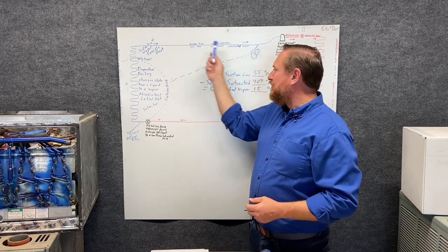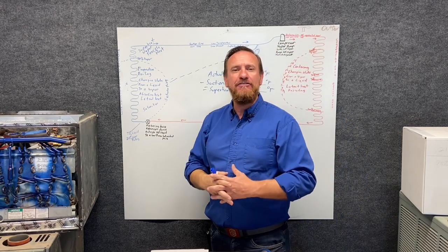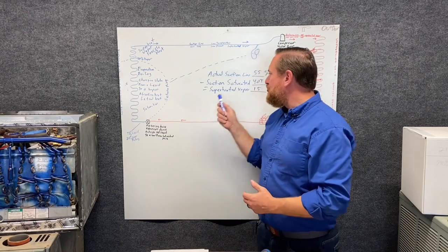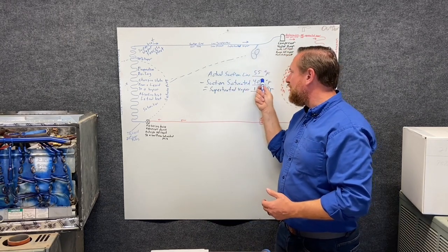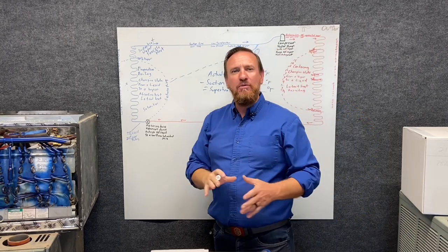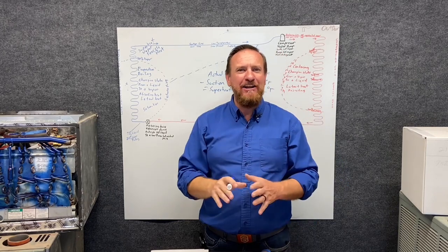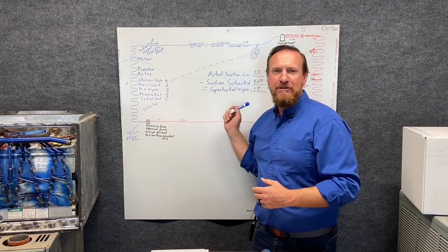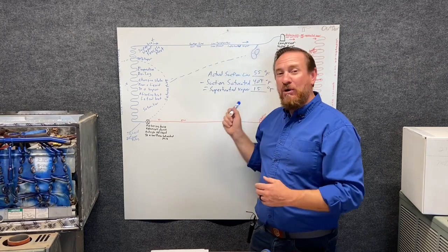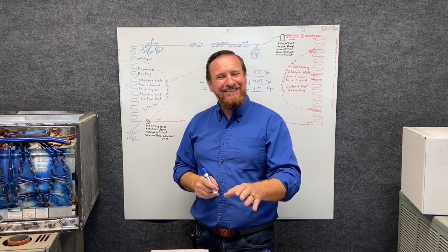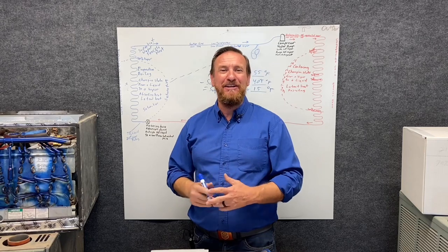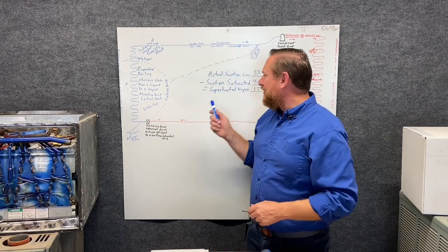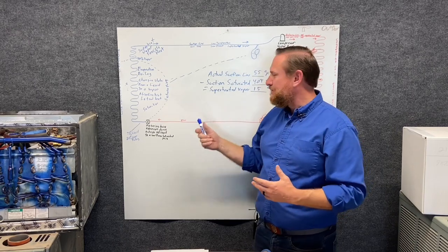This refrigerant is superheated. Now there's tons of different refrigerants, but ultimately, regardless of any refrigerant that you use, once you convert pressure to a temperature and you do this formula, you will always have a reading that's going to be valuable. Regardless of when the temperatures and pressures change, this number is going to be valuable. Now we can't talk about what number is a good number yet, because we still have a whole lot more to learn. It depends on our metering device and some conditions, but we will get there. So this is how to see what the system's doing.